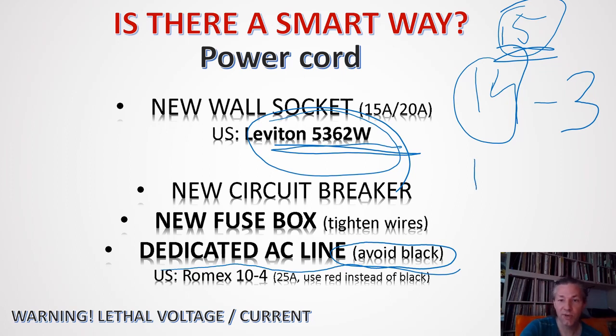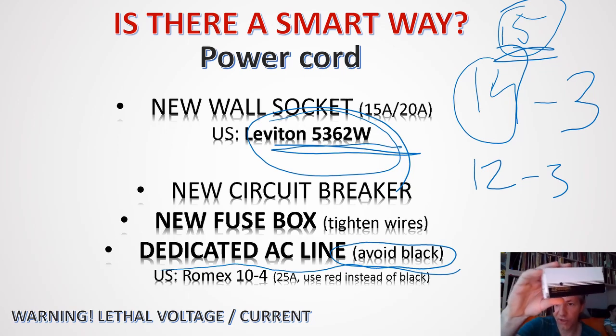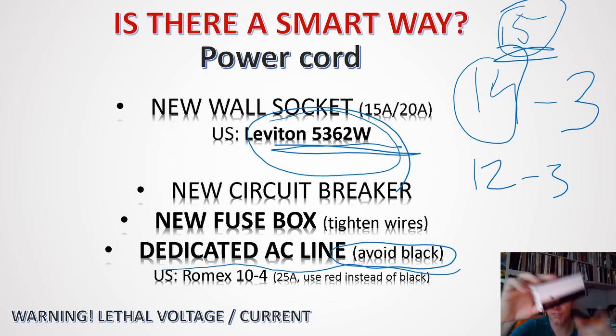If you see something like 12-3, it means the same 3 conductor cable, but 12 gauge, which can carry up to 20 amps. That can handle this Leviton plug. If you use that, also make sure to upgrade your circuit breaker to a 20 amp breaker - the electrician will be happy to do that, and it's up to code.